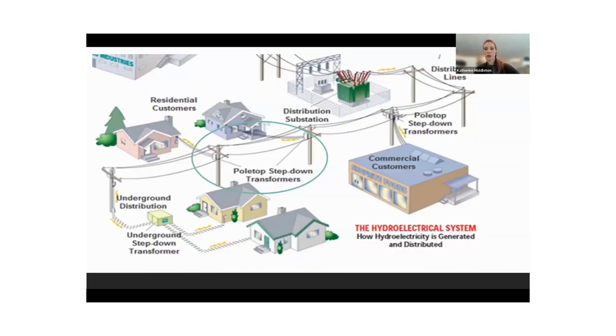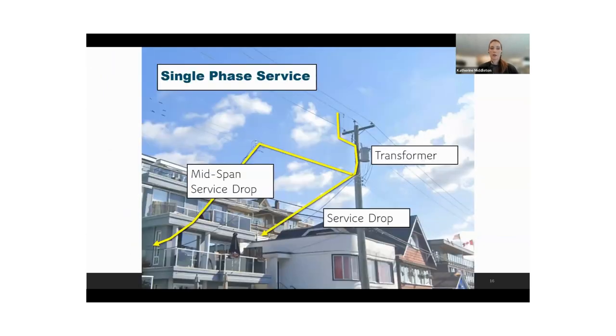Then getting into single phase services, this is typically what you're going to see for residential homes. Residential customers are fed from what we call a single phase service, instead of three phase transformers. Instead of the three cans you saw in the previous pictures, here you just see a single one. From that transformer, you can see on the middle line there are service wires, and from there we're feeding two houses from that one transformer. There's a limitation to how many customers or houses a single transformer can supply, based on customer load, the size of the transformer, and how far away that transformer and secondary wire can run before we run into voltage drop issues.